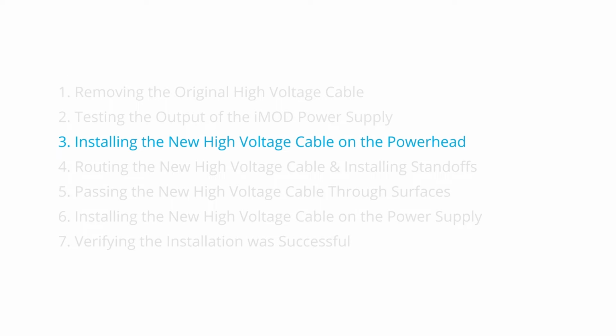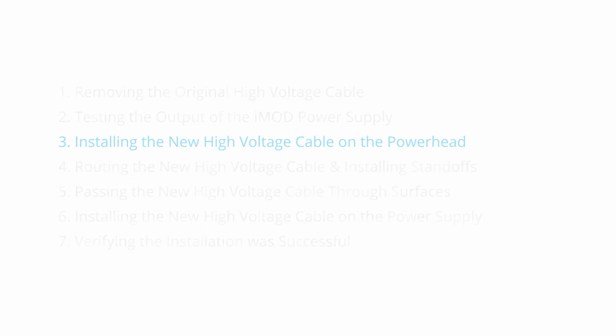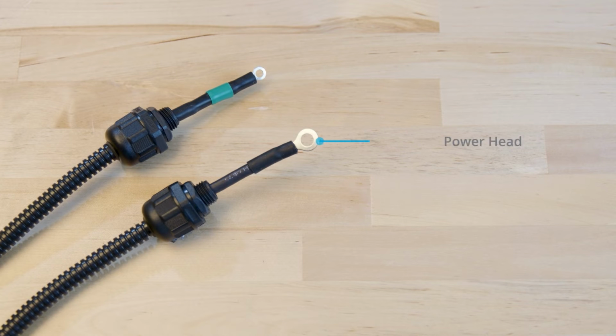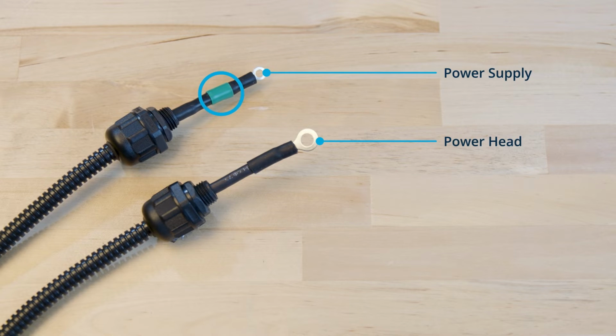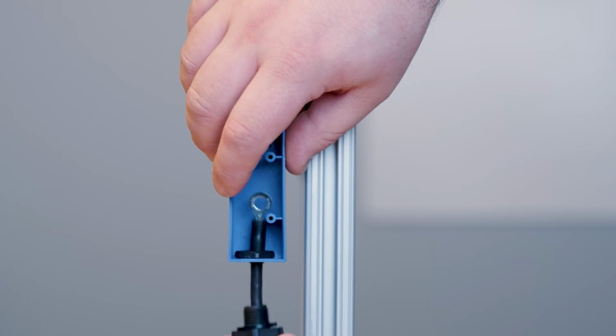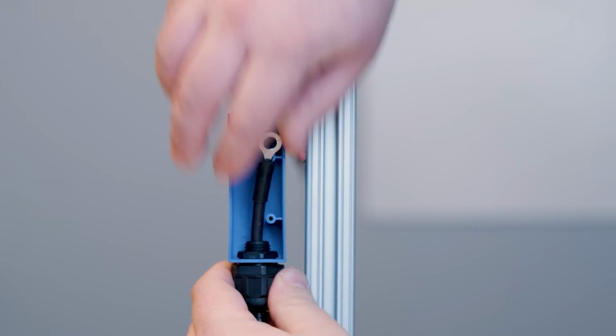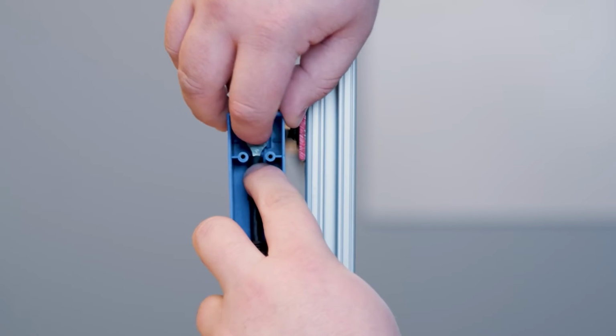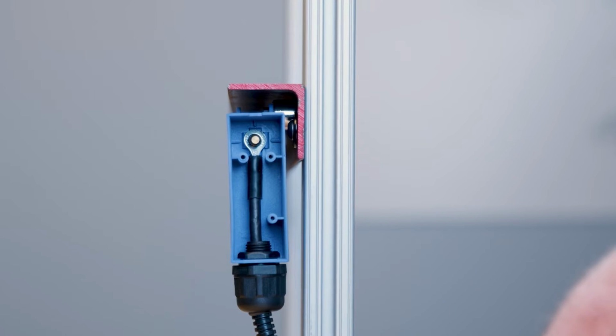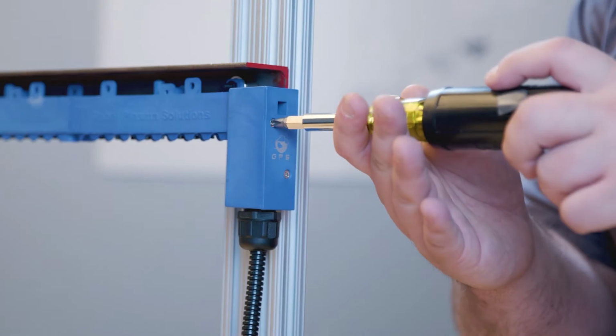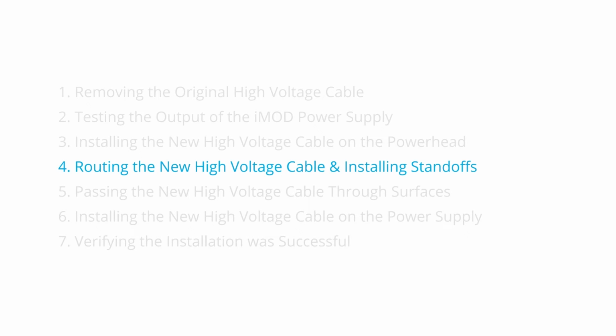Step 3. Installing the new high-voltage cable on the power head. During installation, ensure the larger ring terminal connector goes to the power head and the smaller ring terminal connector goes to the power supply. The new cable will have a green indicator on the power supply side. Thread the cable through the power head assembly and tighten the retaining nut on the cable gland. Position the ring terminal connector on the post within the power head. Reinstall the back plate of the power head. Step 4. Routing the new high voltage cable and installing standoffs from the power head to the power supply.